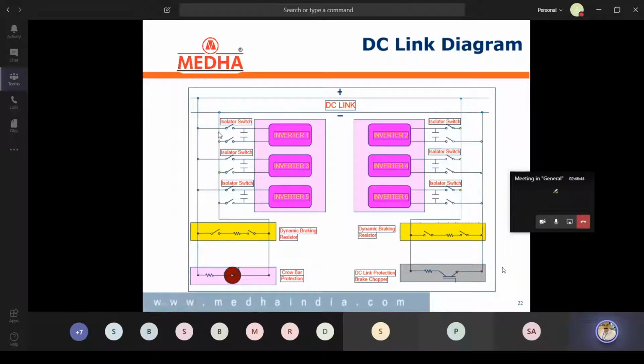Then this DC supply comes to the DC-link capacitor. This acts as an AC ripple suppressor. Pure DC is given to each and every inverter. Total 6 inverters are there. If the contactor closes, pure DC supply comes to the inverter, and as per the computer commands, these inverters convert the DC into 3-phase VVVF, variable voltage variable frequency outputs, and that supply goes to the motors for individual motor operation. Further, through B1, B2, B3, B4, 4 braking contactors are there inside the ECC1. When we go for dynamic braking or self-loading, at that time the system automatically energizes these braking contactors so that the generated power will be dissipated through these grid resistors.